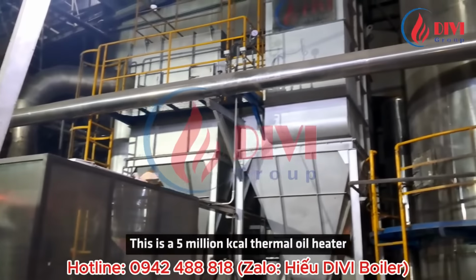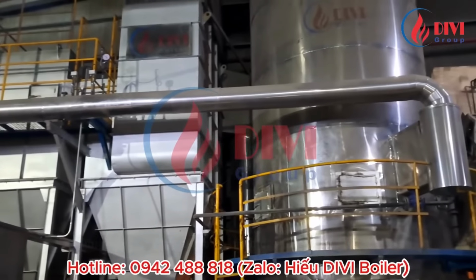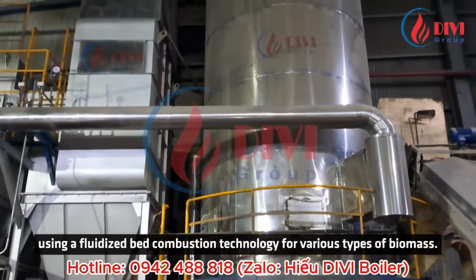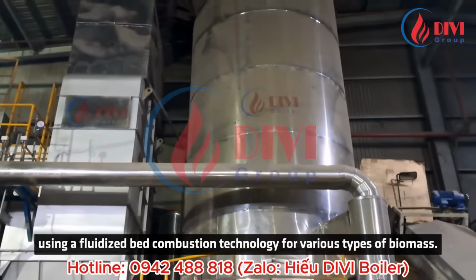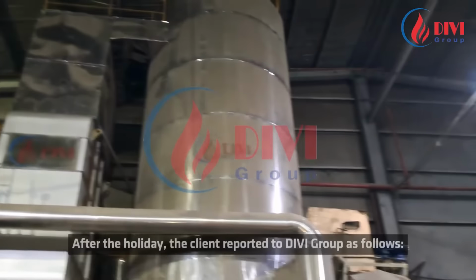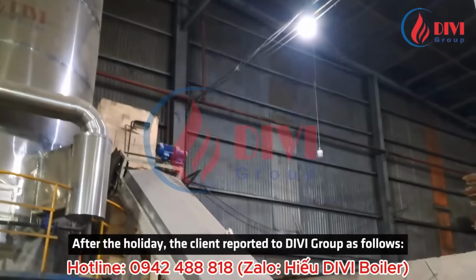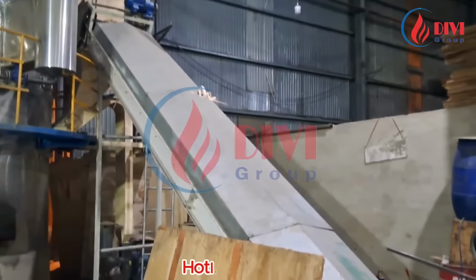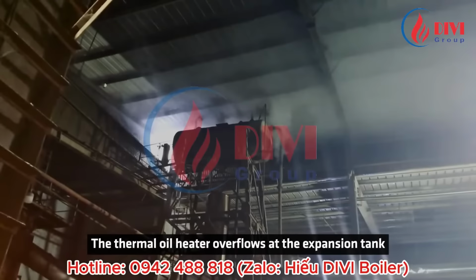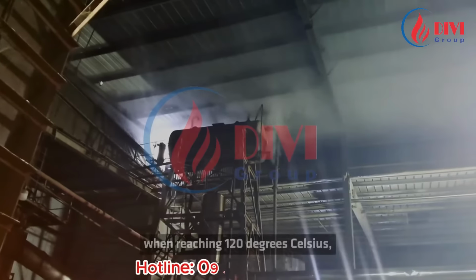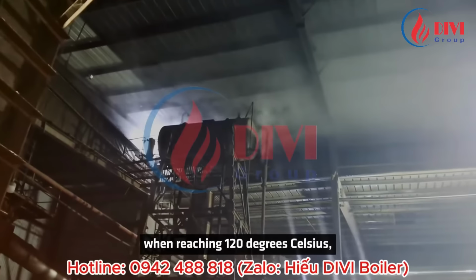This is a 5 million kcal thermal oil heater using a fluidized bed combustion technology for various types of biomass. After the holiday, the client reported to DIVI Group as follows. The thermal oil heater overflows at the expansion tank when reaching 120 degrees Celsius, and the pump pressure drops.